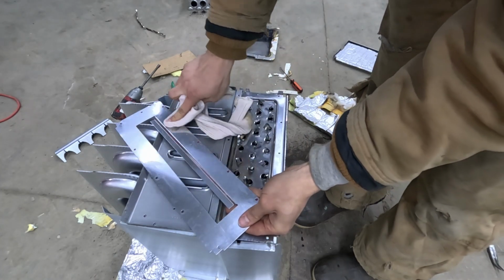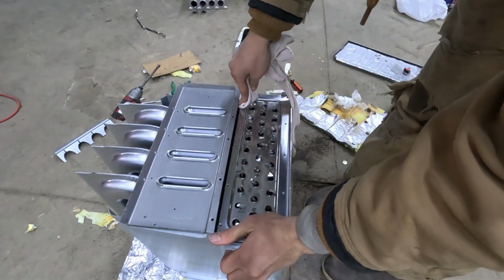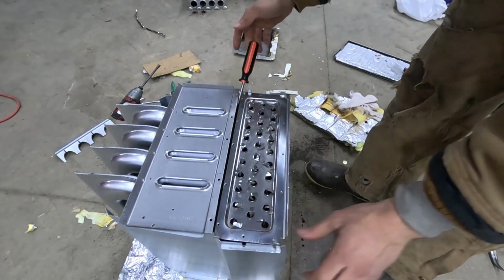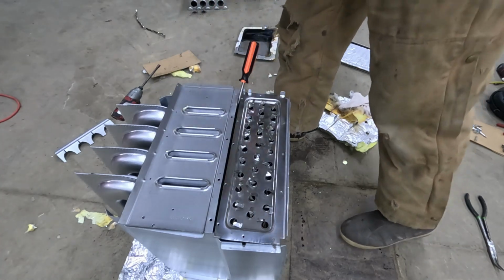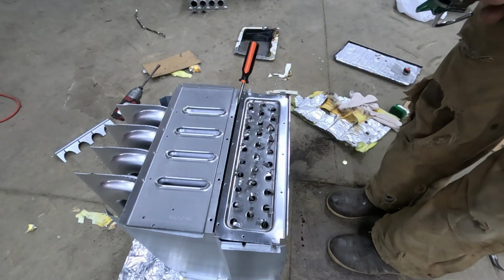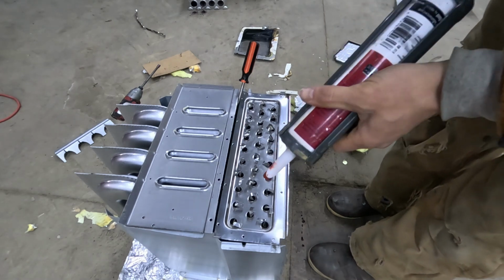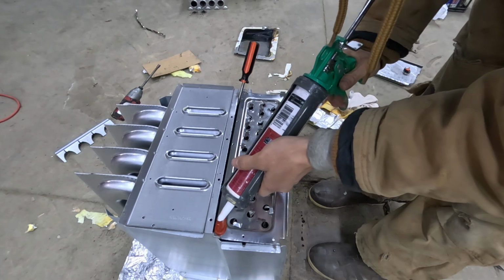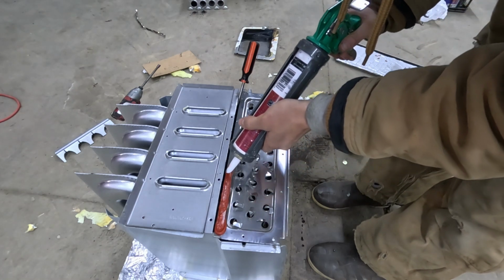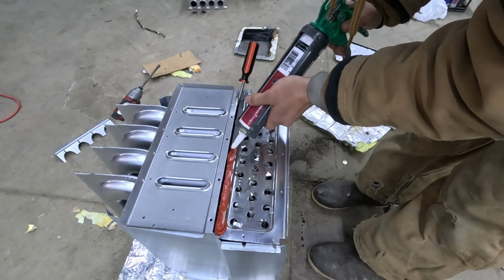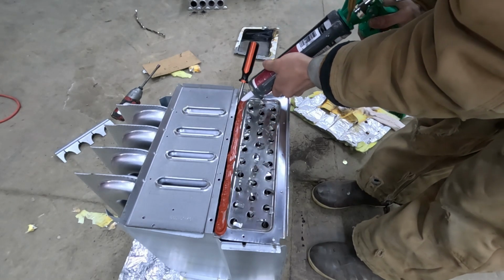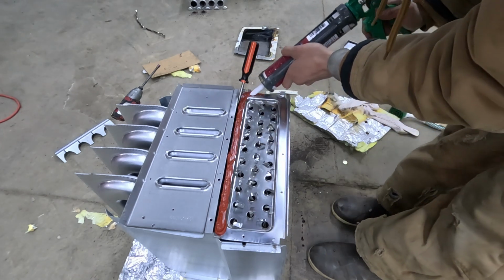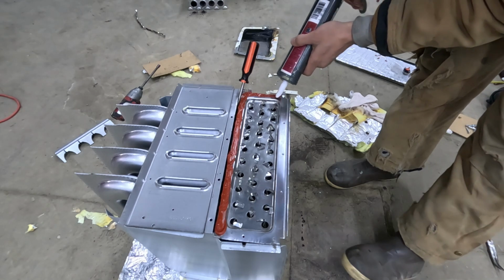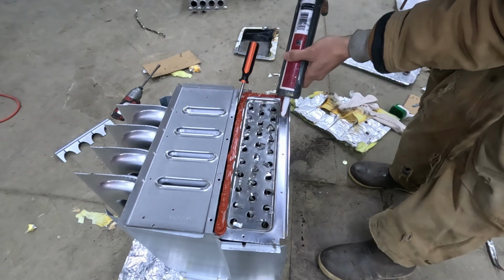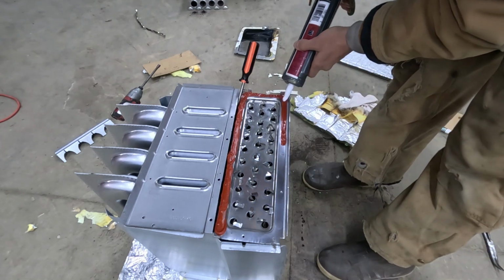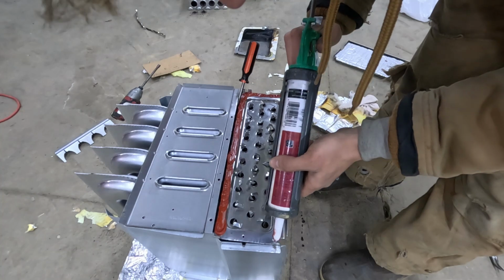Carefully wipe down these surfaces here, and we'll stick this screwdriver in here to give us a little clearance from that. Then we'll go ahead with our high temp silicone here, and we don't want to put so much that it squeezes out and blocks off anything in the heat exchanger. Try to have it a little heavier toward the outside than the inside, but definitely go over the screw holes so there's silicone on either side, because we don't want it leaking.